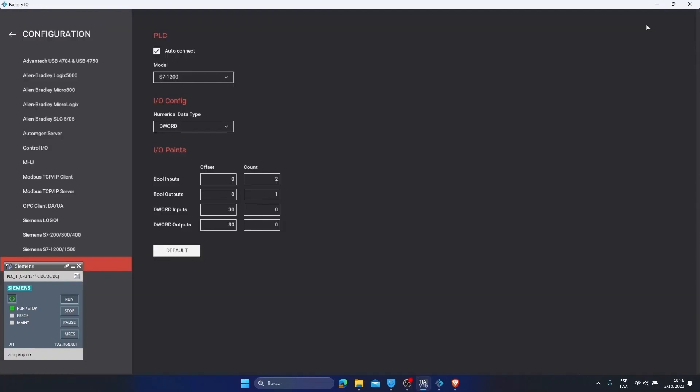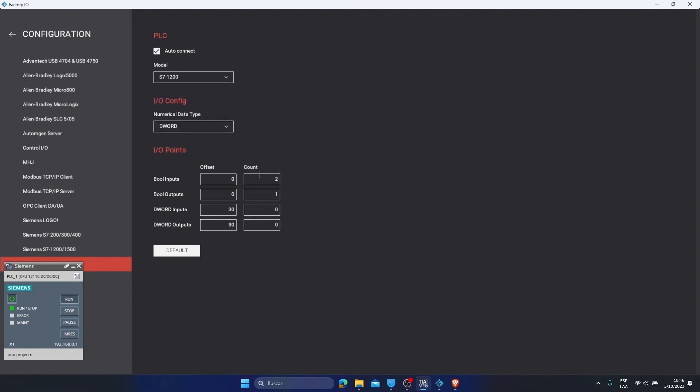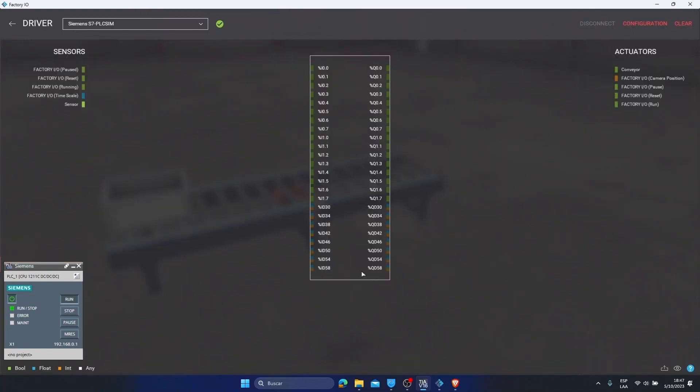We go to configuration and select the model. Now we are using an S7-1200 PLC, but if you are using a 1500 or a 300, then we just do it. Select settings. This is where we are going to increase our inputs and our outputs. By default, they normally set it to 16. By default on the output, we are going to set it to 16. You can also do that by just setting it here as default. I am going to put it in default better so that you can do it in front. And look, I put it in default and automatically 16 inputs and 16 outputs appeared, type bool. And these would be the analogues. We click OK.